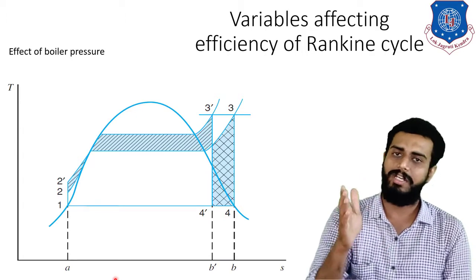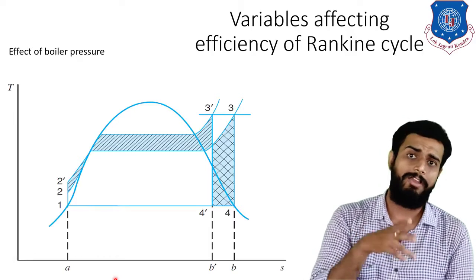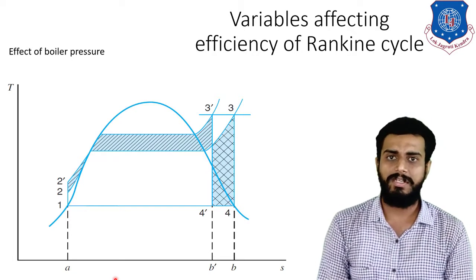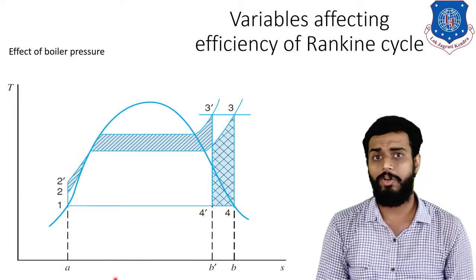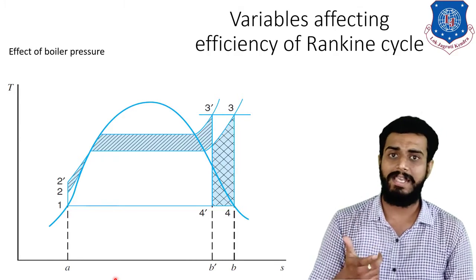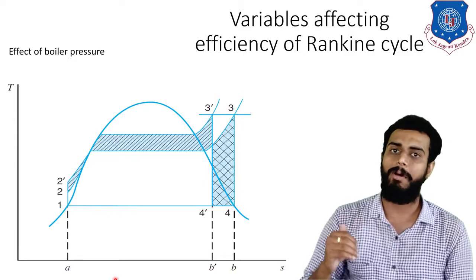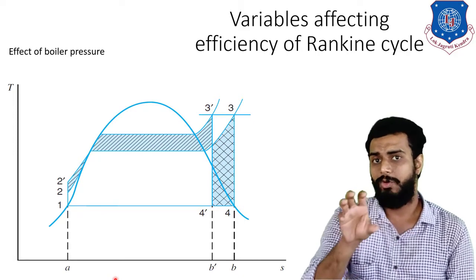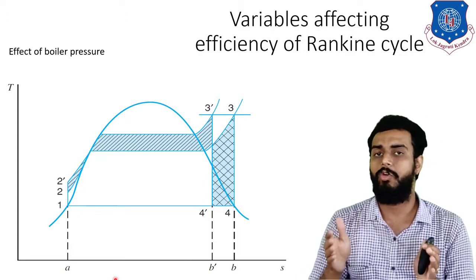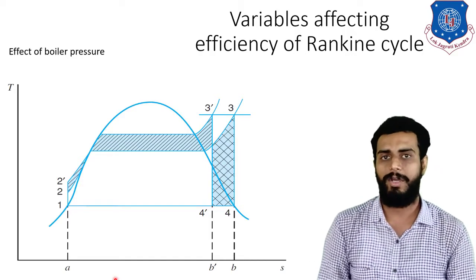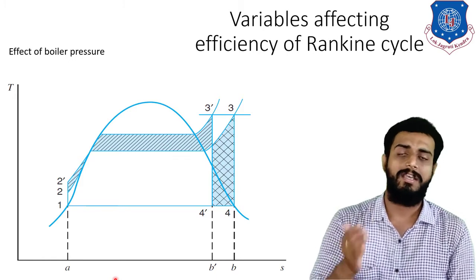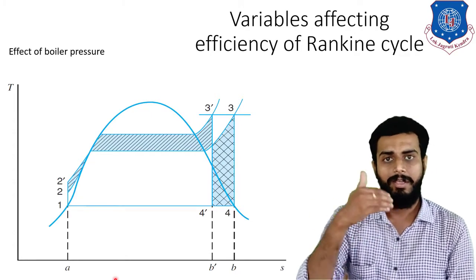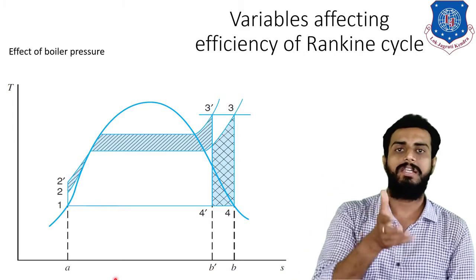To summarize: if you increase the boiler pressure, decrease the condenser pressure, or superheat the steam, the efficiency of the Rankine cycle will increase. However, in a real-life power plant, using any single factor to increase efficiency will not be noticeable compared to the investment made. In real life, if you want to increase efficiency significantly, one should go for a combination of these effects — not only a single effect — which is why we discuss reheat, regenerative, and other combined cycles.